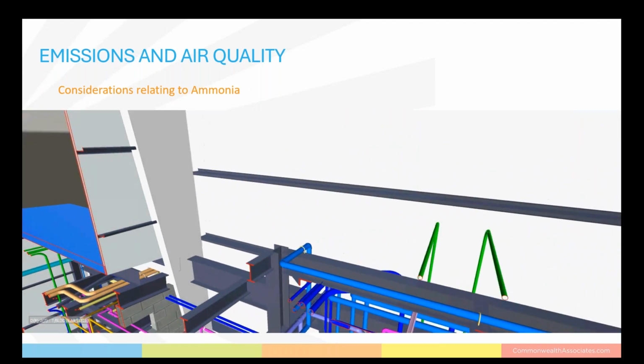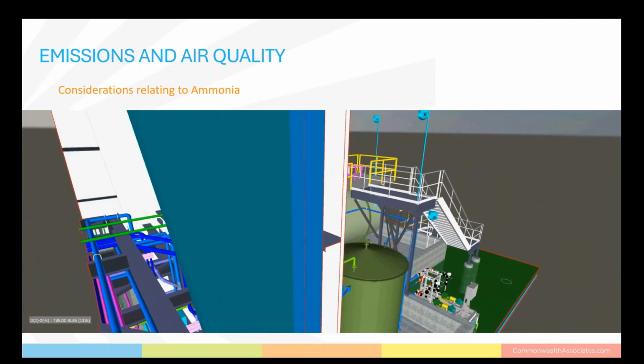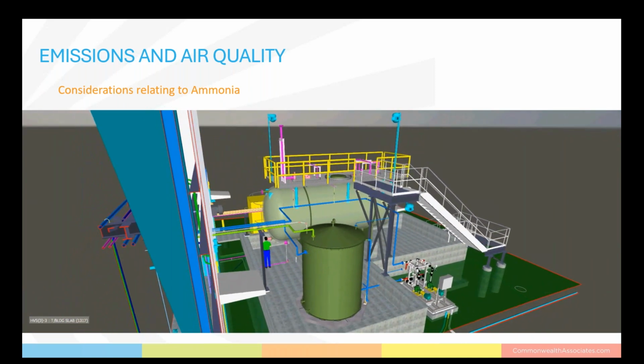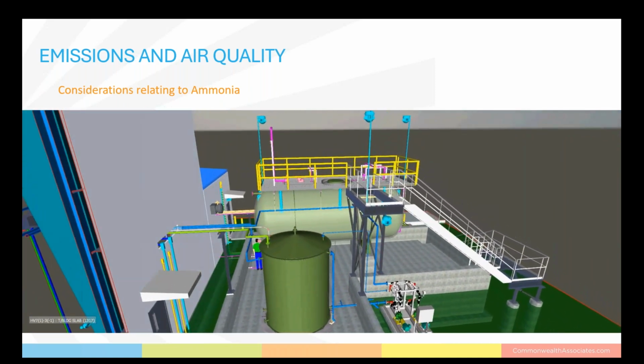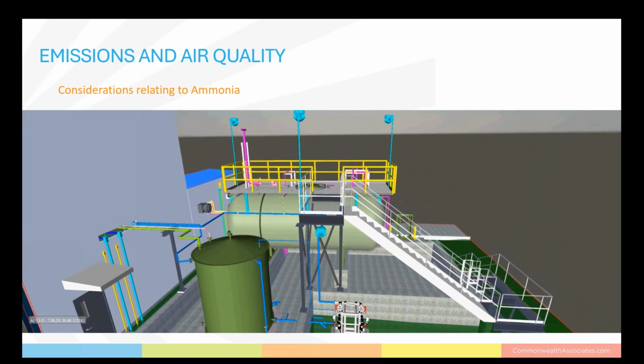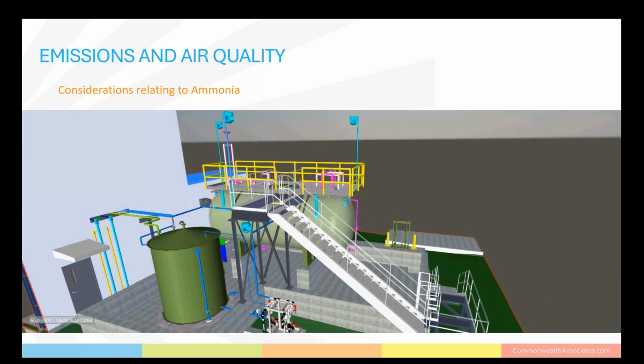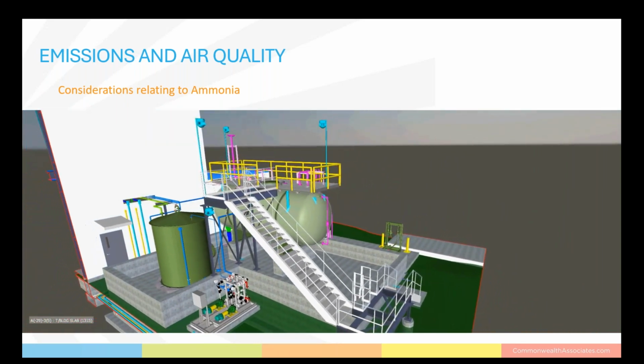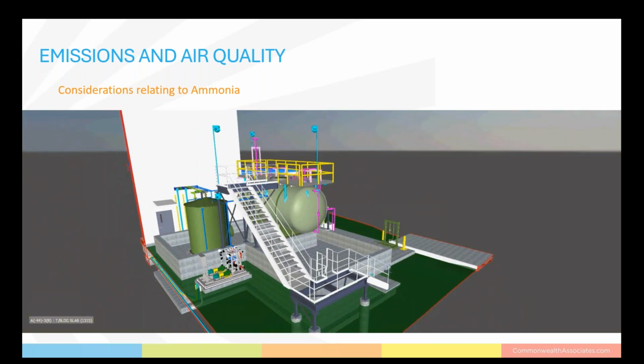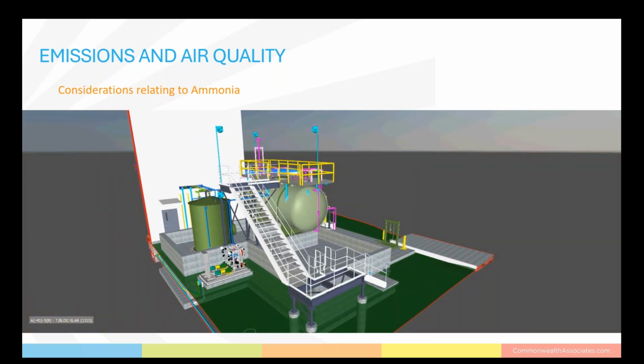As we rotate back out of the building, we'll get a better look at the containment. In this case, we had a nearby chemical tank, and we were able to utilize one containment for both tanks. That containment volume must be able to accommodate the volume of the tanks plus 10%, and also allow for extra capacity for rain, snow accumulation in an outdoor situation.